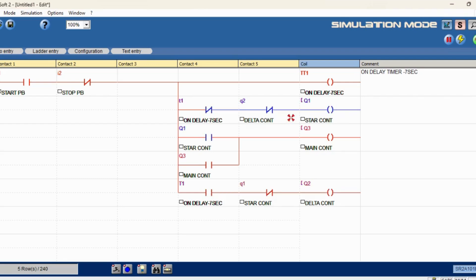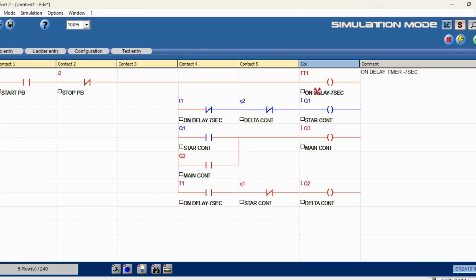We have started. You can see the main contactor is activated, star contactor and timer also activated. After the preset 7 seconds, the delta contactor switched over from star to delta. It is running and keeping on running. While changing — and before also — the main contactor is constantly activated. The main contactor should not be off while changing from star to delta.